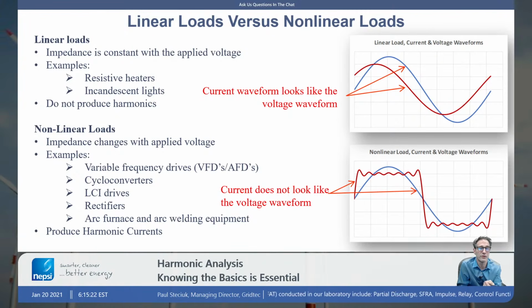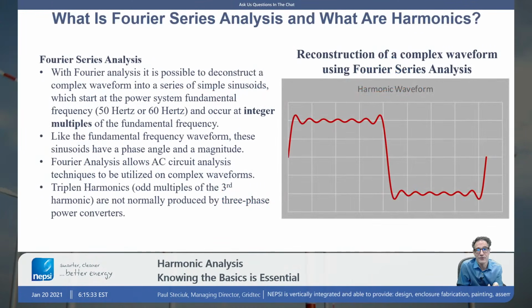But other loads, such as variable frequency drives, cycloconverters, LCI drives, rectifiers, they all have distorted waveforms where the voltage and current do not match. So if I were to ask, well, how do you do that analysis? How can I evaluate the impact of that load on the system? You would have this wave shape here, and it does not follow the standard method of doing network analysis that you learned in college. Because in college we've learned how to work with sinusoids, not with square waves. It's a little bit difficult.